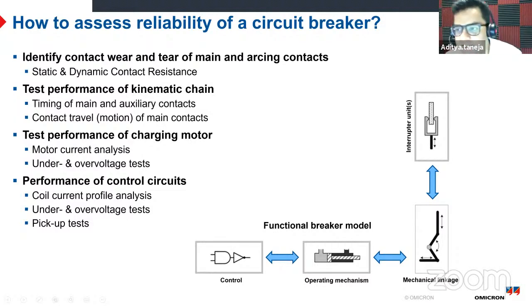Now let's look at the model again, the functional model which we developed in the previous slides. So we have the interrupters, mechanical linkage, operating mechanism, and control. When we are doing the maintenance or the inspection, how can we make sure that we are doing enough tests on these parts to know that when I put it back into service, it will not fail for the next 6 years, for example, or next 3 years, whatever is the frequency. There are different types of problems faced in interrupters. The main one is wear and tear, because it is operating in a high current, high arcing environment, which is quite stressful for breaker contacts. So we need to see the wear and tear.